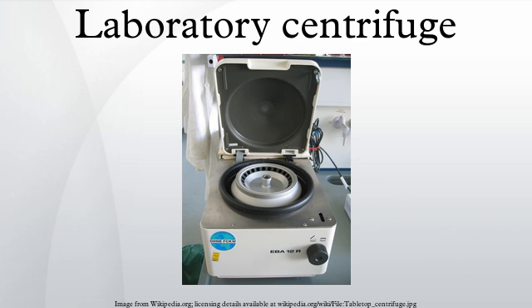Glass centrifuge tubes can be used with most solvents, but tend to be more expensive. They can be cleaned like other laboratory glassware, and can be sterilized by autoclaving. They must be handled with care, since small scratches can cause failure under the strong forces imposed during a run. Glass tubes are inserted into soft rubber sleeves to cushion them during runs.